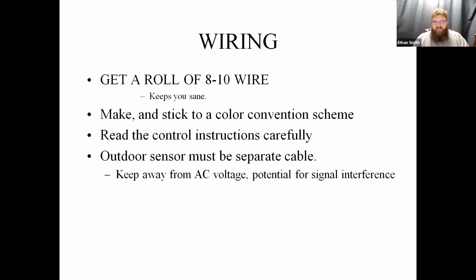Read the instructions, guys. It's not just an e-pad, it is an instruction booklet. Pull it out, make sure you're looking at it. I will tell you guys, if you don't know how to wire a heat pump, the best place to look is not in the furnace, it's not in the heat pump, it's in the thermostat wiring diagrams typically, because it brings it all together.